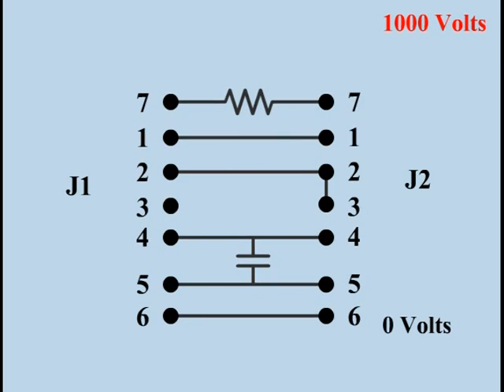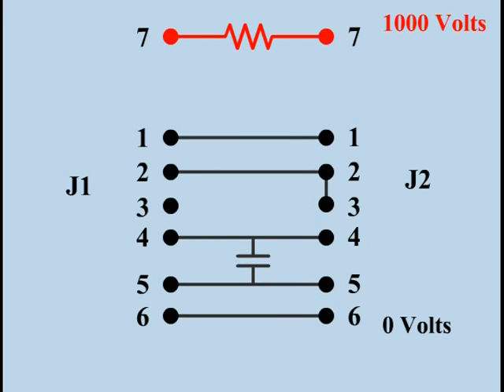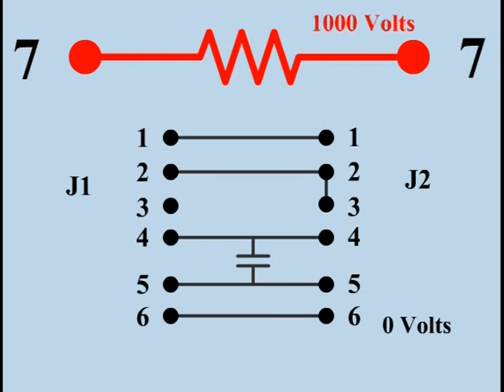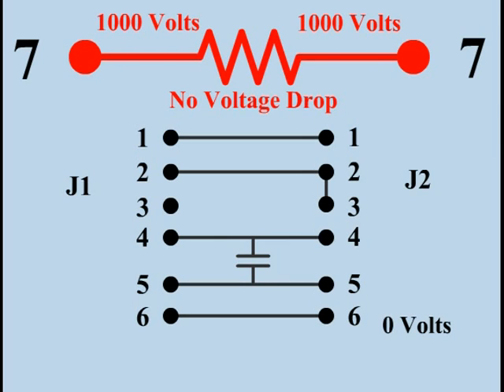Likewise, when we do the hypot test on net 7, the resistor, both ends are electrified simultaneously, which again means no voltage drop across the component and therefore no current flow through it.